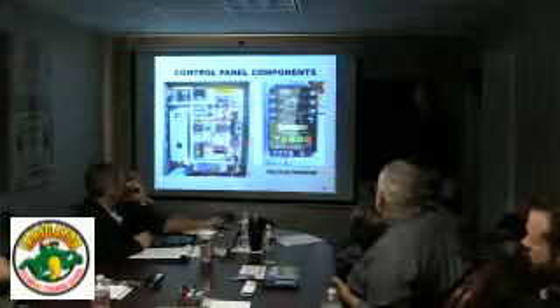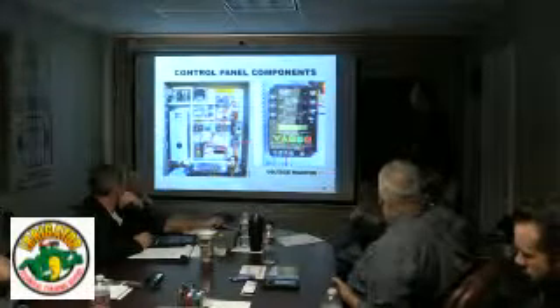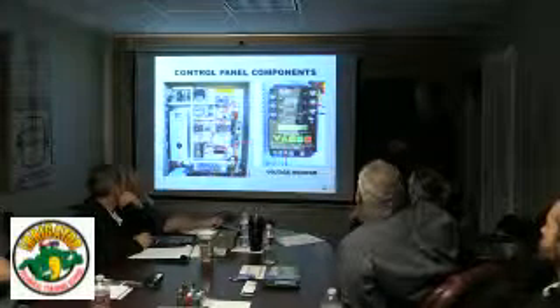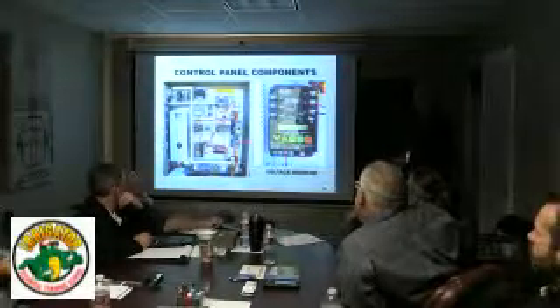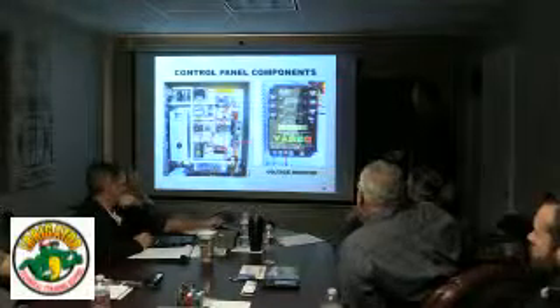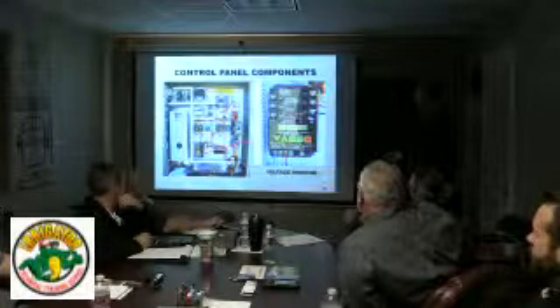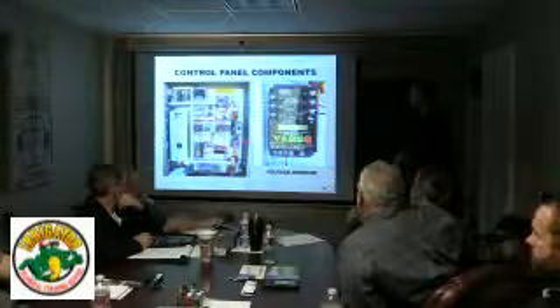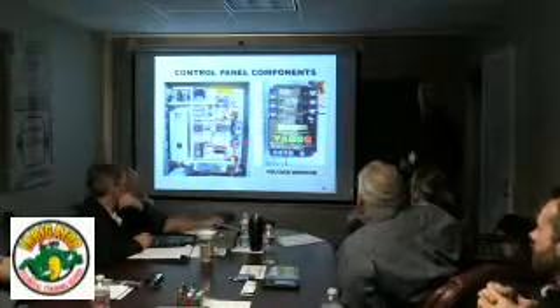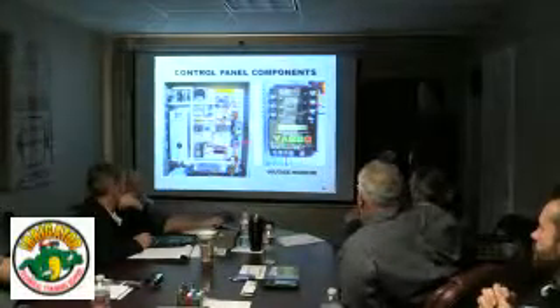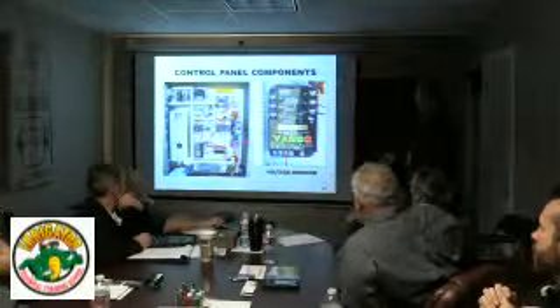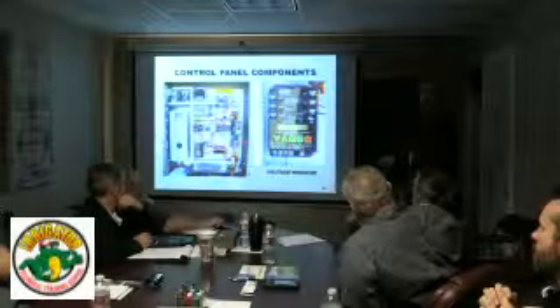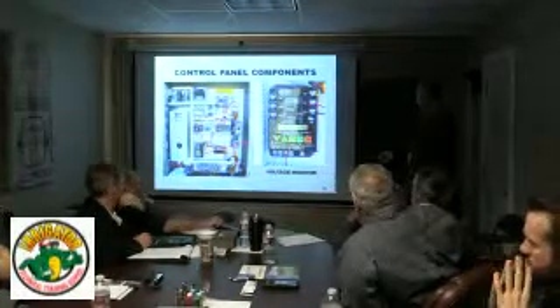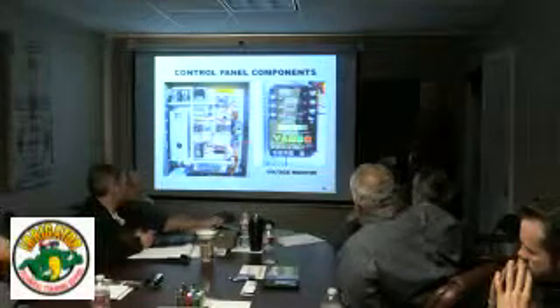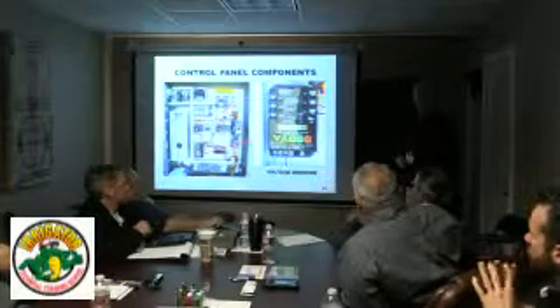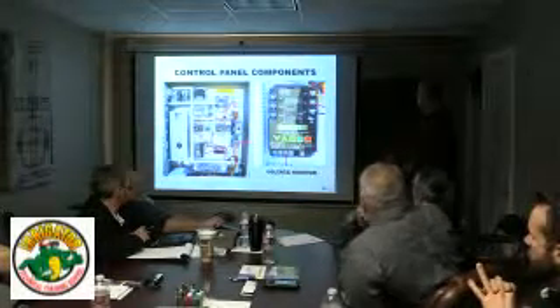Motor saver. We'll look at these in a little more detail tomorrow, but basically they just monitor the phase coming in, and fault on over voltage, under voltage, phase imbalance. Right here it says load energized, and there's a little green LED. That's one thing helpful to keep in mind, make sure that green LED is on. All that load energized means is that they're energizing this coil right here. We've got 24 volt DC right here, and a blue wire going to an input of our PLC. Once this says load energized and voltage is okay, it closes that, and so the PLC gets a signal saying that the voltage monitor says everything's fine. So make sure that this LED is on. If it's not, there could be a fault.